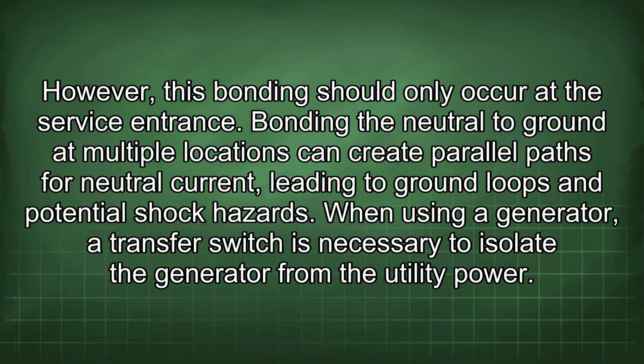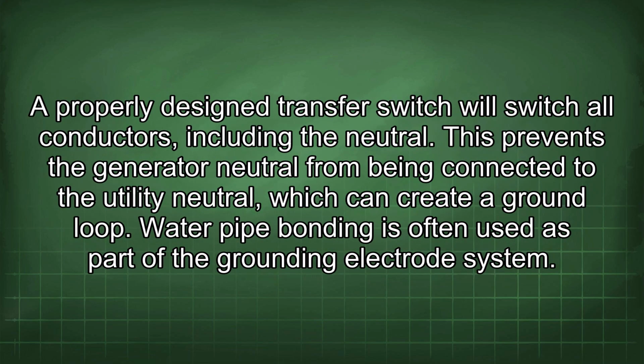When using a generator, a transfer switch is necessary to isolate the generator from the utility power. A properly designed transfer switch will switch all conductors, including the neutral. This prevents the generator neutral from being connected to the utility neutral, which can create a ground loop.